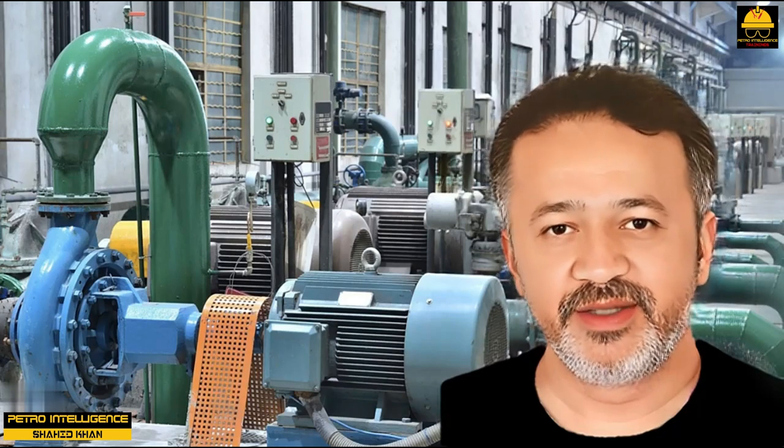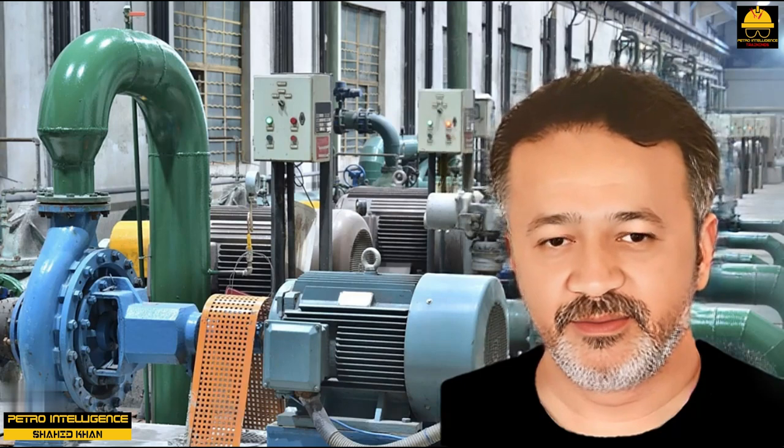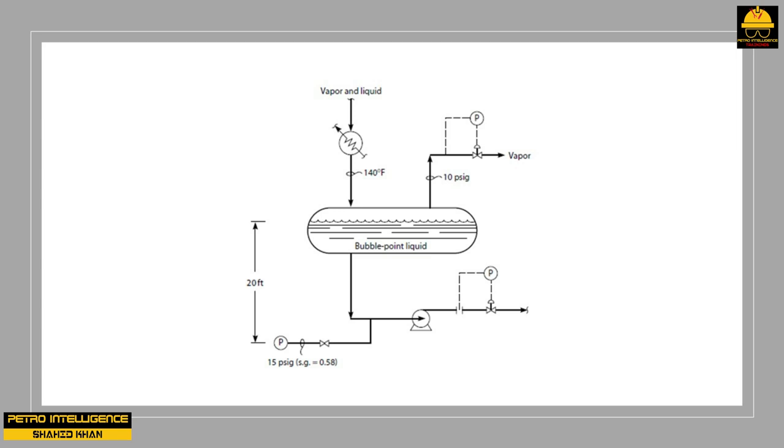The kinetic energy of the liquid increases by a factor of 256, that is, 16 squared. This large increase in kinetic energy comes from the pressure, or feet of head, of the liquid itself. The conversion of the pump's suction pressure to velocity in the eye of the impeller is called the required net positive suction head, NPSH.